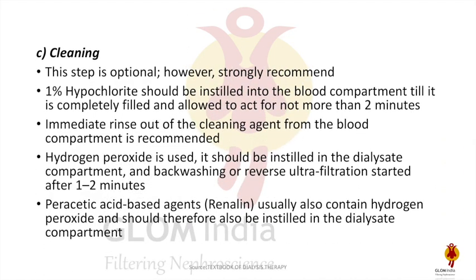The cleaning step is optional. 1% hypochlorite can be instilled into the blood compartment until completely filled and should not be kept for more than two minutes — immediate rinse must follow. For hydrogen peroxide, however, it needs to be instilled into the dialysate compartment, not the blood compartment. Backwashing or reverse ultrafiltration should be started after one to two minutes. Renalin, which also contains hydrogen peroxide, is again to be instilled into the dialysate compartment.